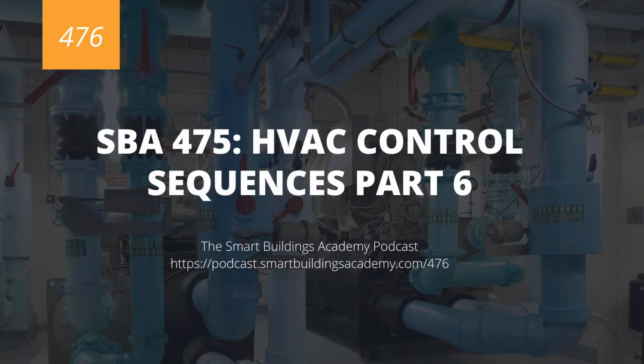From that point, we move on to valve control, and this is where we're going to enable our valve, and then we go to pump control, flow status, chiller enable, and temperature control. I'm going to dive through each one of these in greater detail. So as I mentioned, system enable is typically brought about by either schedule, call for cooling or load, or outdoor air temperature. From there, we have our valve control.